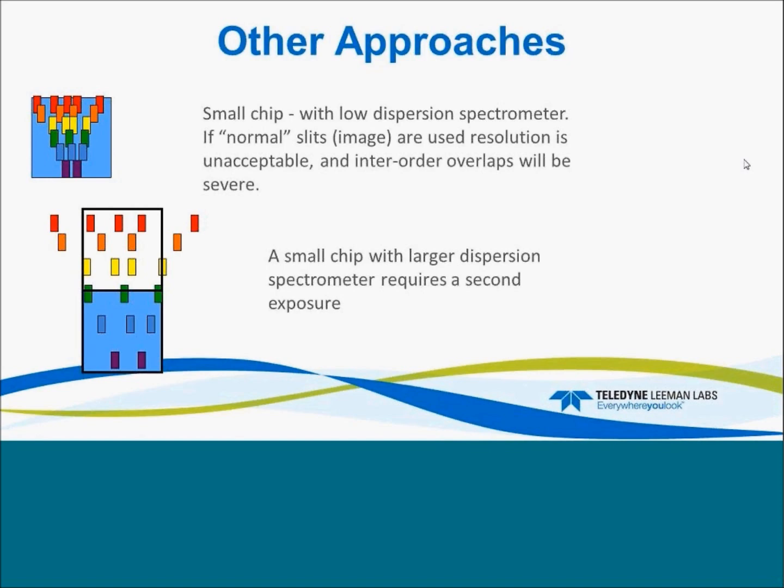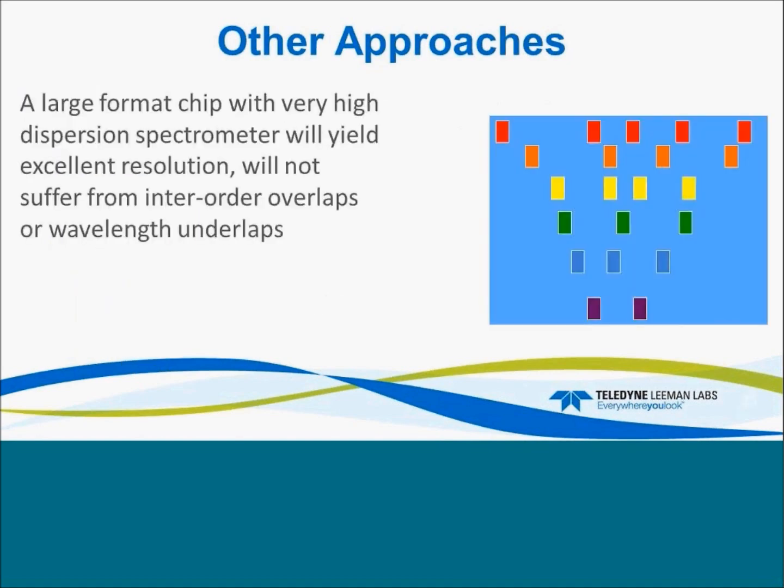Or you can go with, there's different ways, you can go with two separate detectors of a smaller size. All those solutions weren't acceptable to us, but once the large array detector became available that we could fit everything on with one reading, that is the reason that we went with the CID detector. The benefits of also the non-destructive readouts and the random access integration make the device much more flexible for ICP.